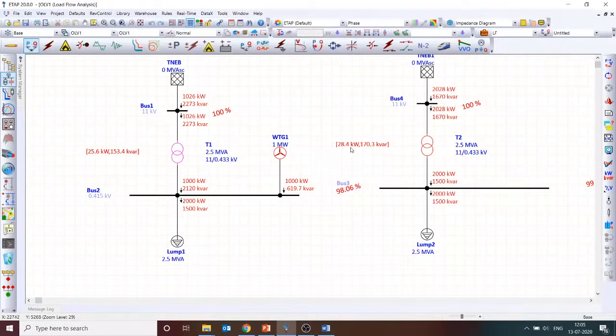Fine. So I have added here the demand is 2000 kilowatt. With the losses, it is 2028 kilowatt here. Here the demand is 2000 kilowatt, but I am generating 1000 kilowatt. The point I am trying to stress is that the wind turbine generator capability is 1 megawatt, only when the wind speed is rated wind speed or above, then it will generate this capacity. If the wind speed is less, then it will not generate. And if it is less than cut-in wind speed, it will not even generate the power.